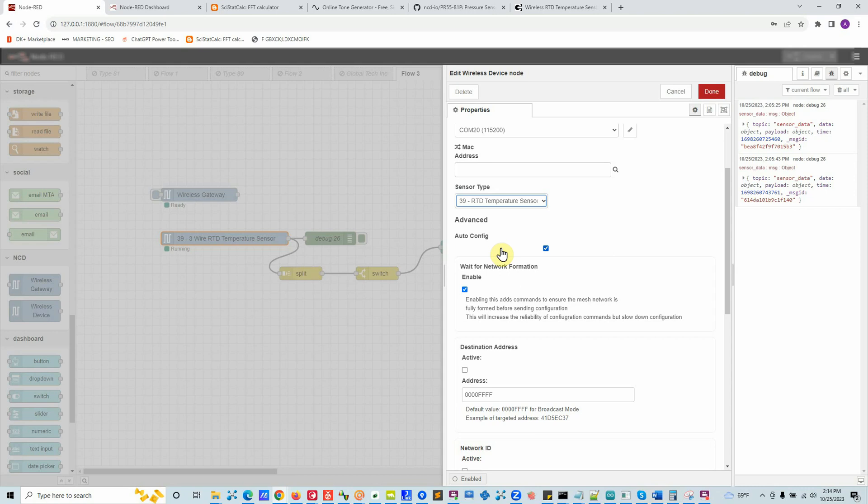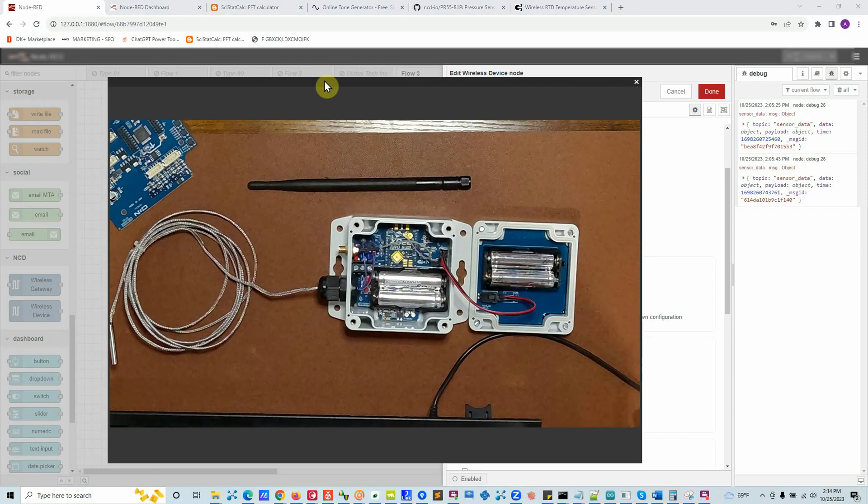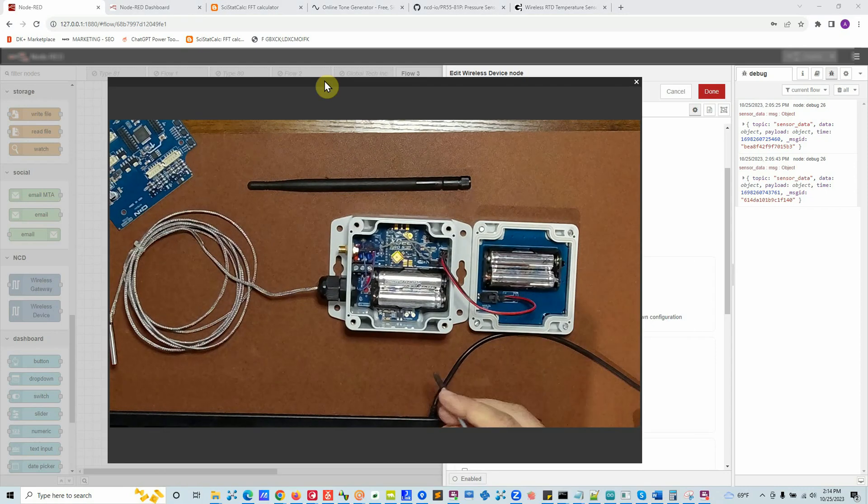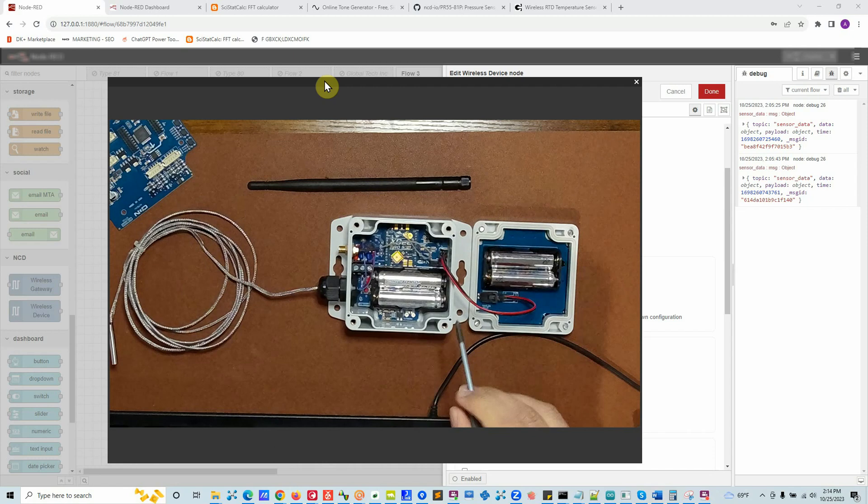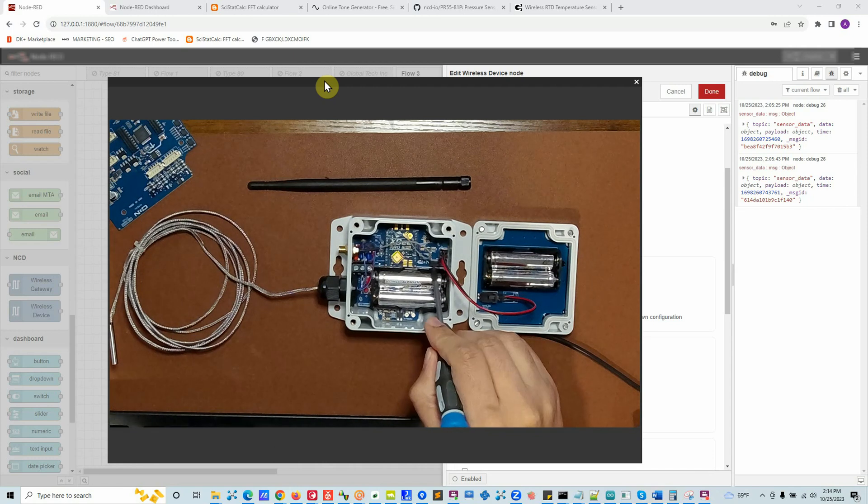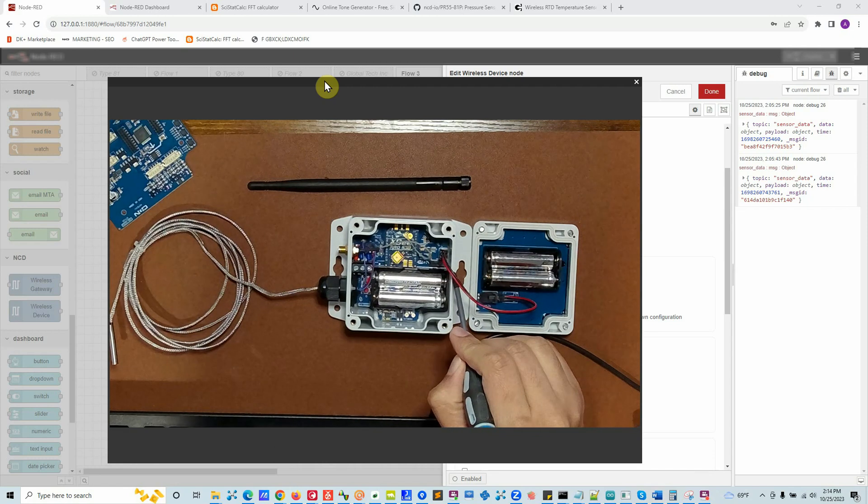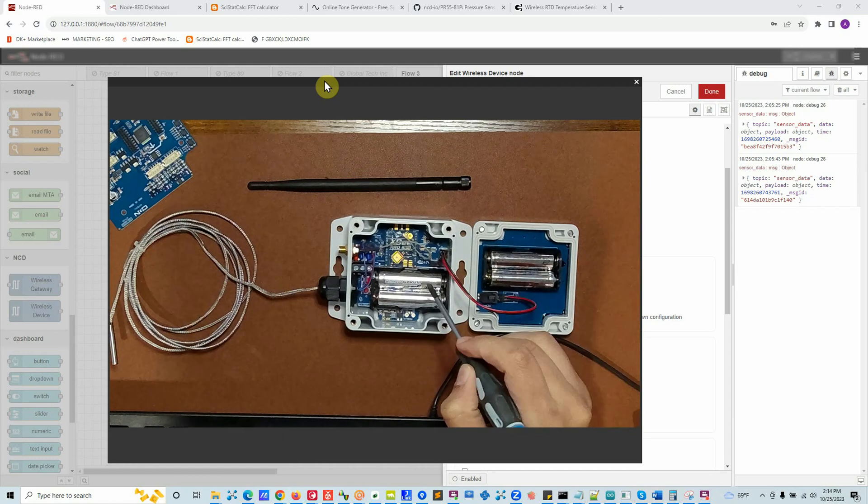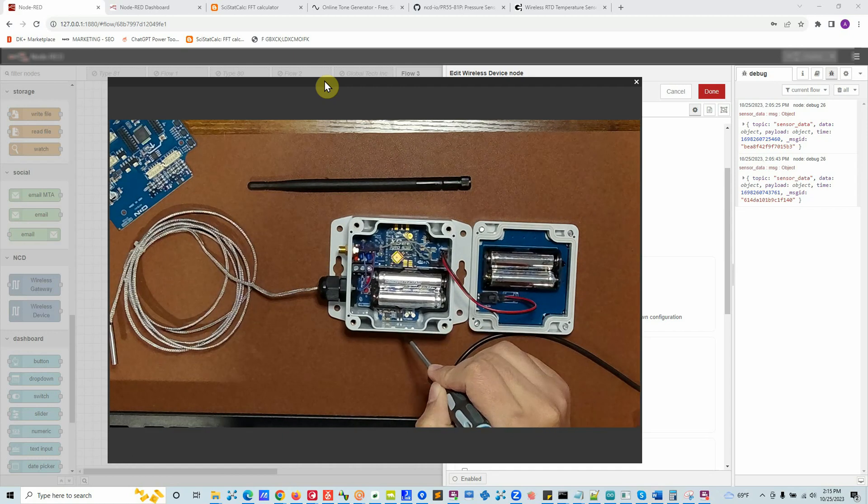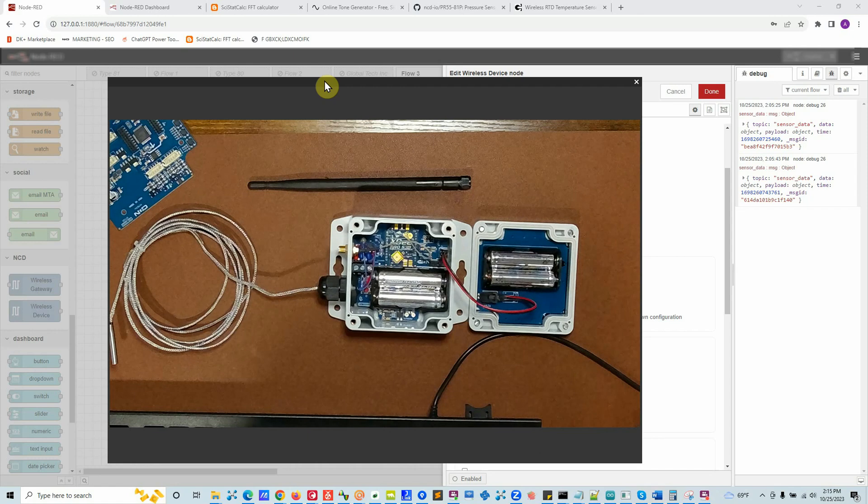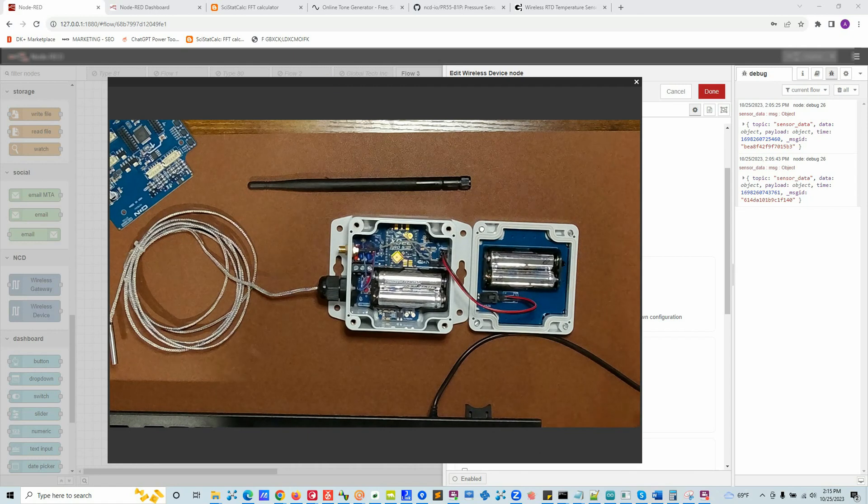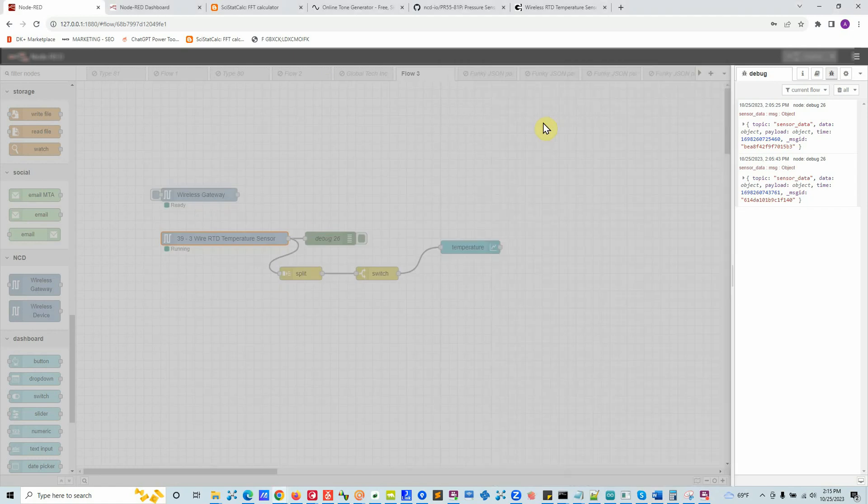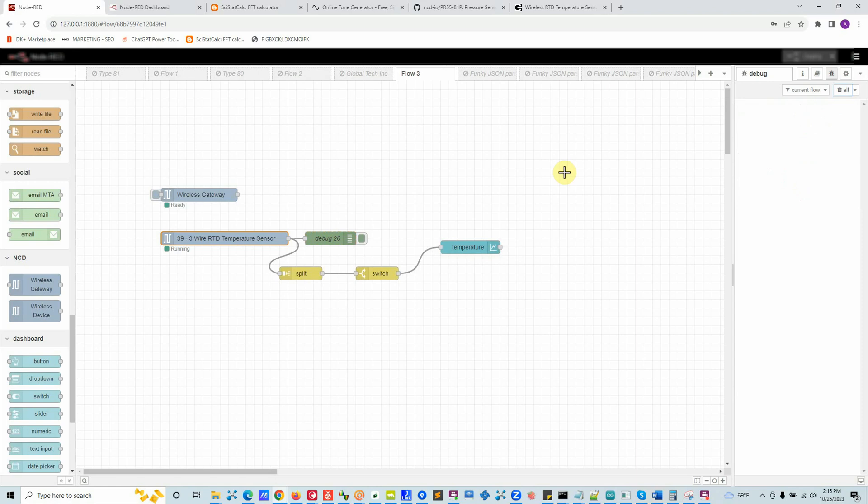When using in the field, you should be using a little bit of higher duration so that the battery does not drain that quickly. One thing I forgot to mention: the sensor can be purchased with batteries only or batteries with external power supply. When the switch is set towards the wall of the enclosure, it will be using the batteries to power it up. If it is away from the wall, then you'll be using the external power supply to power up the electronics and send data.